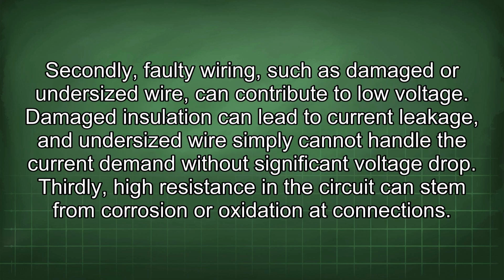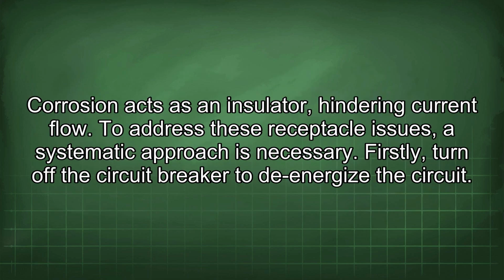Secondly, faulty wiring, such as damaged or undersized wire, can contribute to low voltage. Damaged insulation can lead to current leakage. An undersized wire simply cannot handle the current demand without significant voltage drop. Thirdly, high resistance in the circuit can stem from corrosion or oxidation at connections. Corrosion acts as an insulator, hindering current flow.